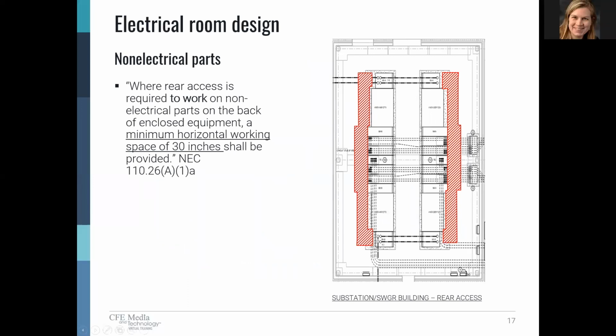So oftentimes, equipment is also required to have rear access, and this is often directed by the equipment manufacturer. What the NEC here tells us is that if the specific equipment requires rear access, this is the minimum working space that you shall provide. In this case, it's 30 inches. So the point really here is that the requirement for rear access is specific to the type of equipment being provided. Switchgear is a good example of distribution equipment that requires both front and rear access.